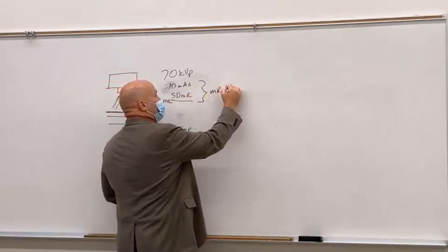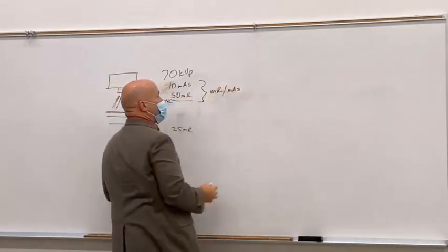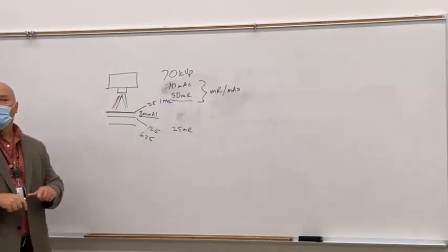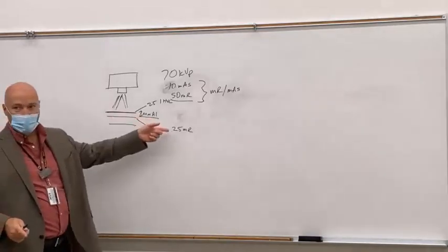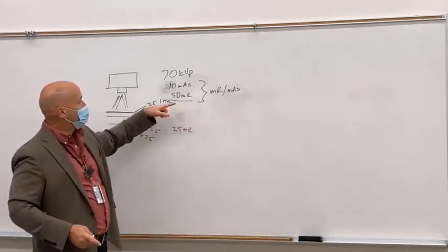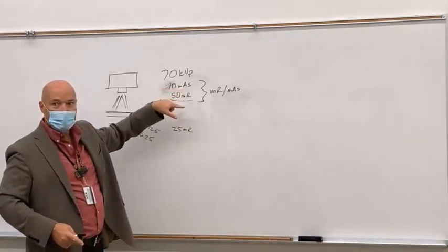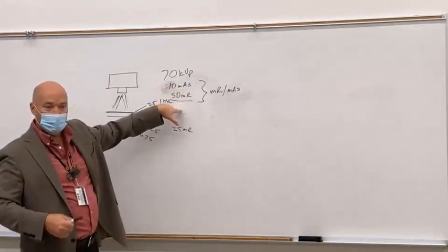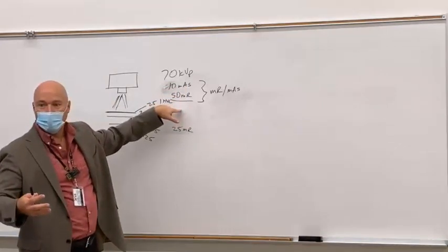One thing that he's going to do is an mR/mAs output, all right? The purpose for this particular test is to make sure that for that 10 mAs, he gets 50 mR, relatively speaking, right?